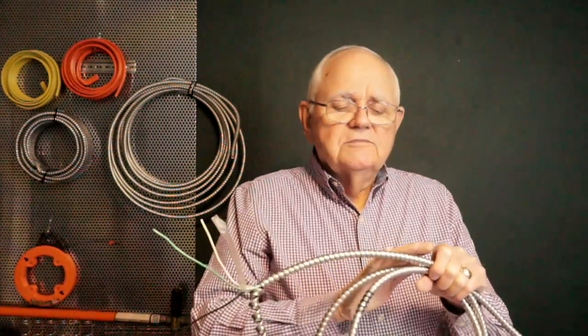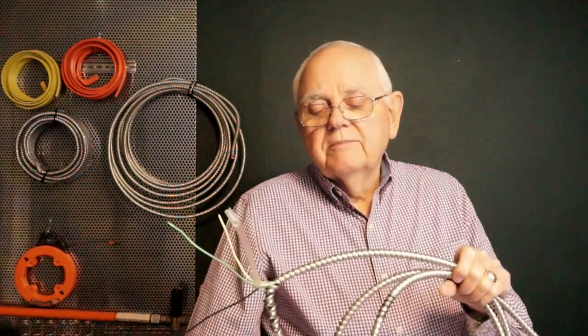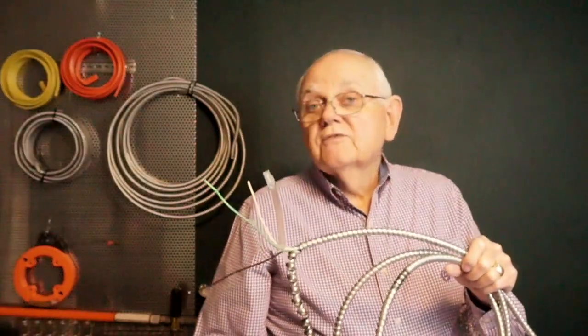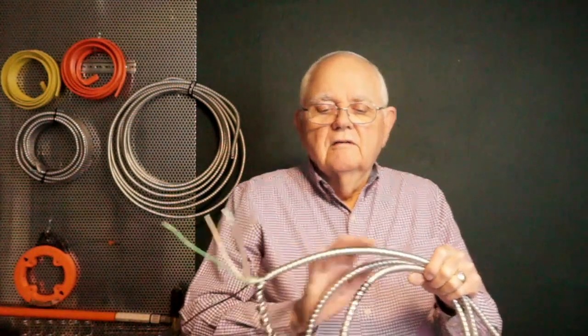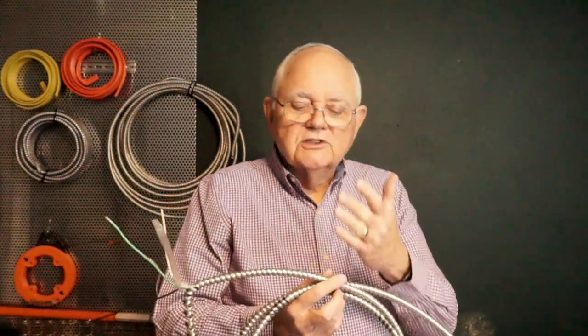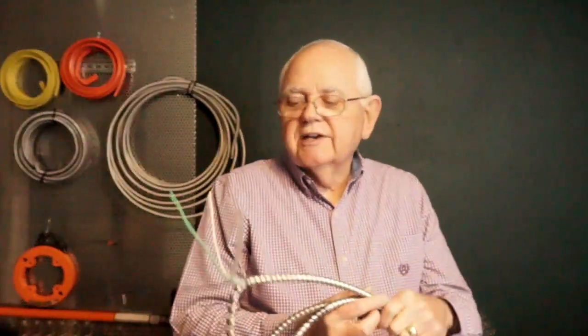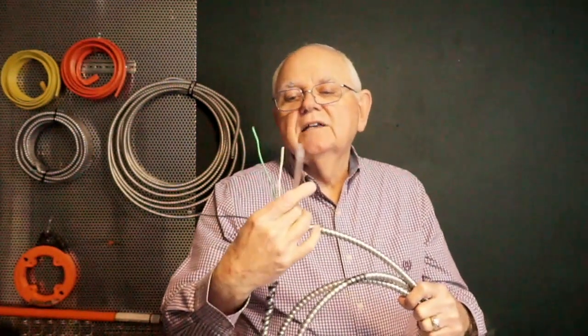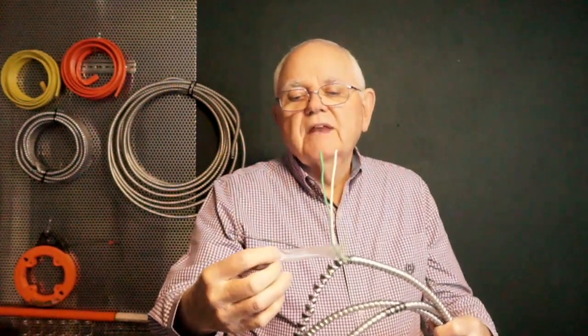And that type of cable, often referred to as health care cable, specifically manufactured for our applications, will have that green color to it. So anyway, be aware of that. Not required, but pretty common then. And then they can use other color codings as well. So we've talked a lot about metal-clad cable so far, how it's constructed, the three types of sheaths that we can have, conductors on the inside, the transparent plastic tape that binds my conductors together and so forth.